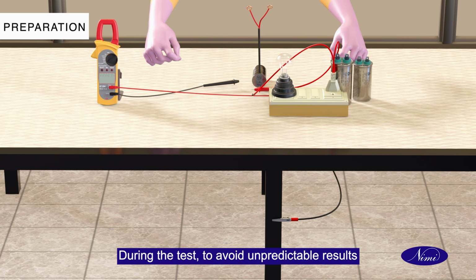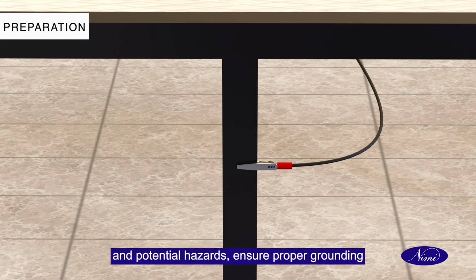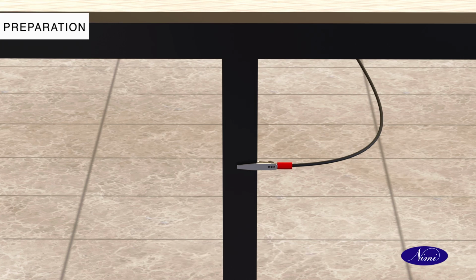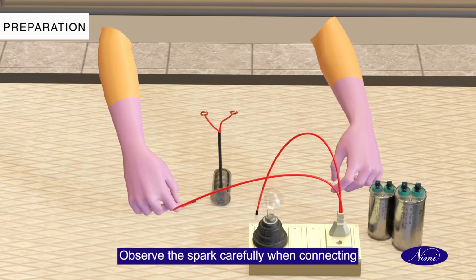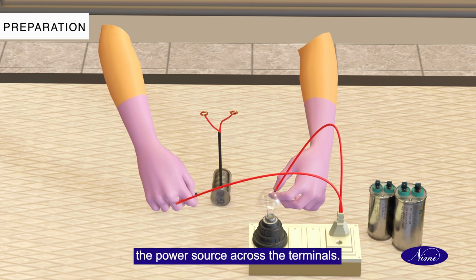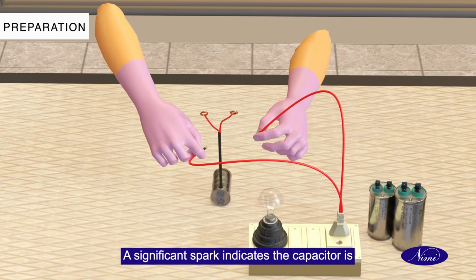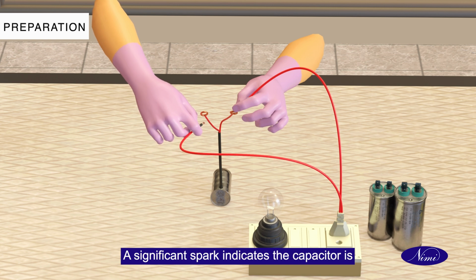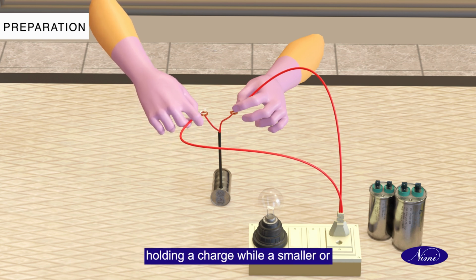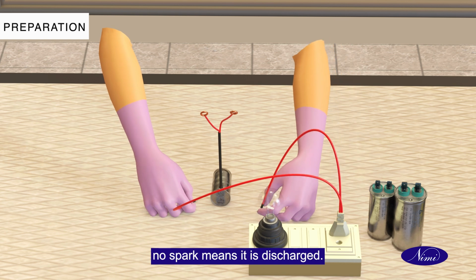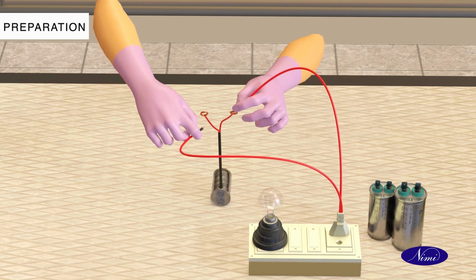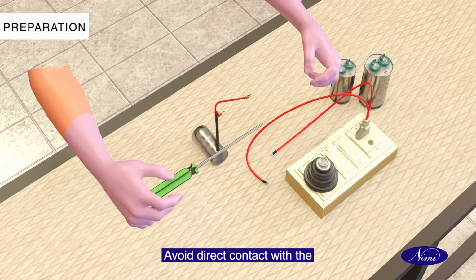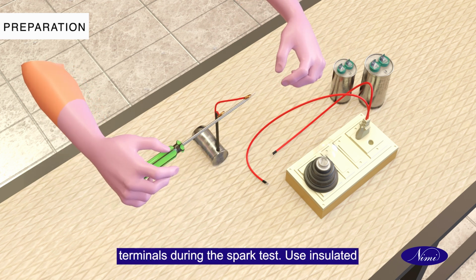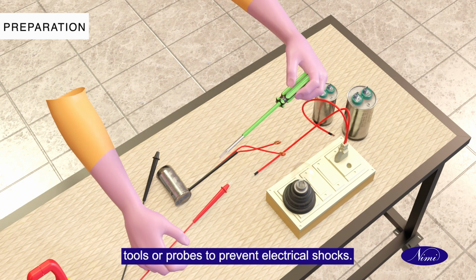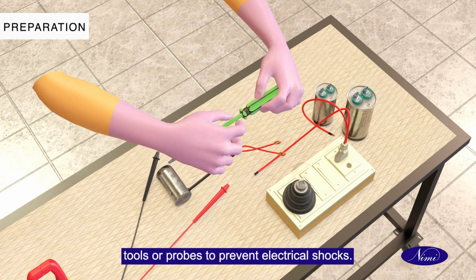During the test, to avoid unpredictable results and potential hazards, ensure proper grounding of the capacitor terminals. Observe the spark carefully when connecting the power source across the terminals. A significant spark indicates the capacitor is holding a charge, while a smaller or no spark means it is discharged. Avoid direct contact with the terminals during the spark test. Use insulated tools or probes to prevent electrical shocks.